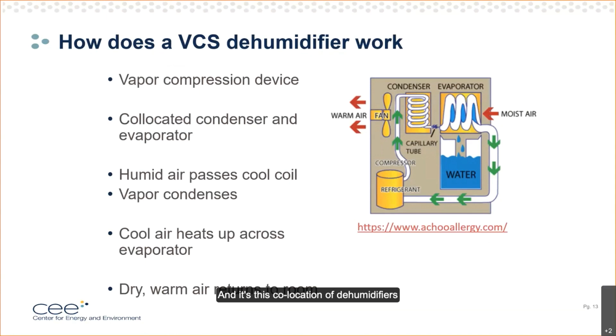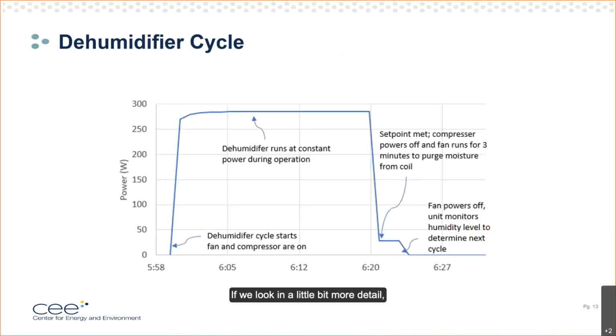And it's this co-location of heat exchangers that lets dehumidifiers control humidity levels. Since they're not going to overcool the space, they can monitor humidity and then turn on and off based on that humidity level. So if we look in a little bit more detail, dehumidifiers can run continuously. If they were doing this in practice, they wouldn't meet the load. So they'd be calling for a constant need of dehumidification. In most cases, though, they cycle. That is, they turn on and off as they meet the set point.